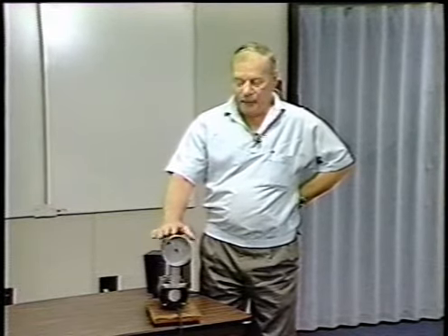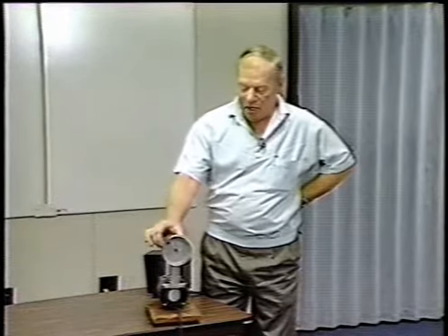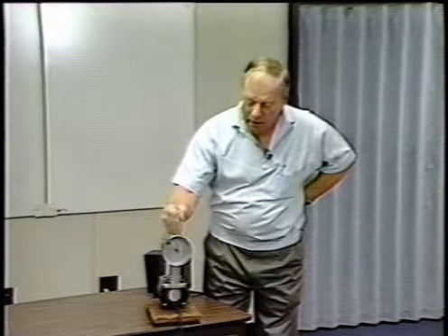One of the more common problems that you run into on rotating machinery today is a thing we refer to as resonance. Basically, every object and every element of a machine has its own natural frequency based on its mass and stiffness. For example, if you just consider this upper bearing of this particular structure right here, it has a very, very low stiffness in the horizontal direction, hence it has a very, very low natural frequency or resonant frequency. Vertically, it's considerably stiffer, and that just simply means it has a different vertical natural frequency.